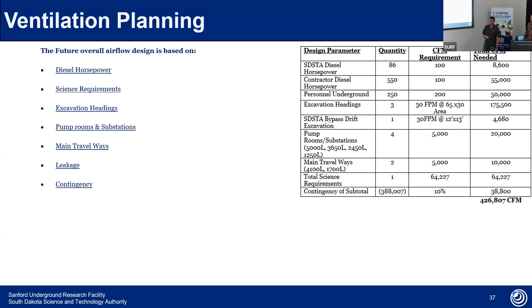So going back to that horsepower, this is just one page of our equipment underground. You can see the column right in the middle here. This is the fully rated capacity of each piece of equipment. If you supply 100 CFM per brake horsepower, we can never meet the overall requirement for that ventilation system.